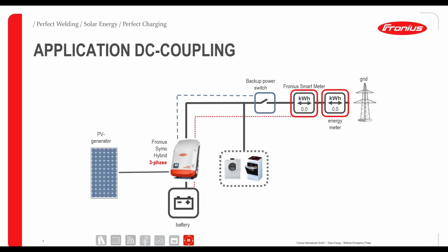And then the last component which is additionally required is the Fronius Smart Meter. This is just after the energy meter, another meter to give us feedback about the feed-in point, more or less. We need to know what's going on at this point, because all surplus energy will be charged into the battery, and therefore we need this smart meter at this position. Basically, this is the basic principle of the system for a new installation.